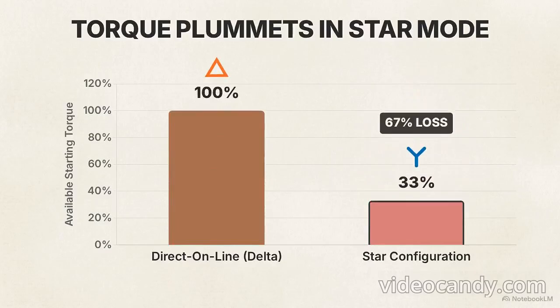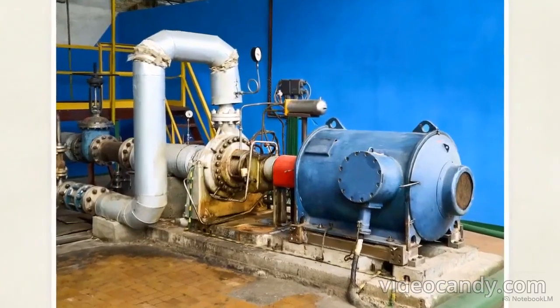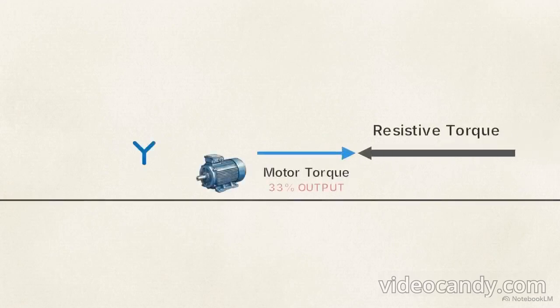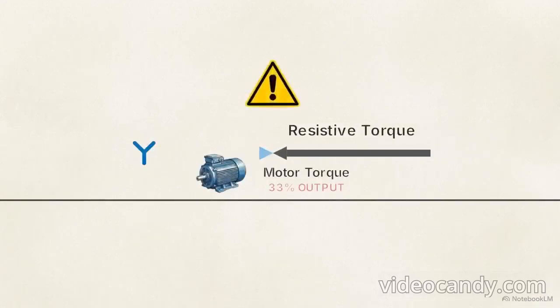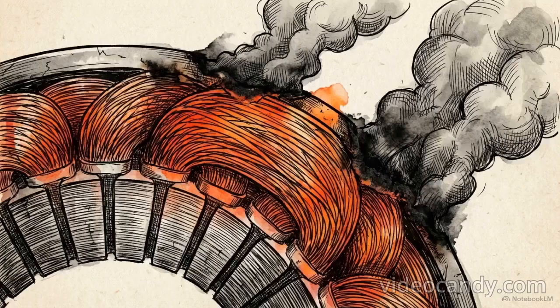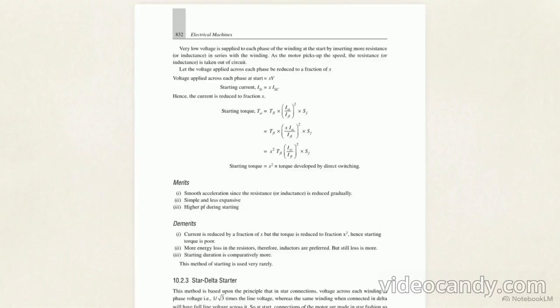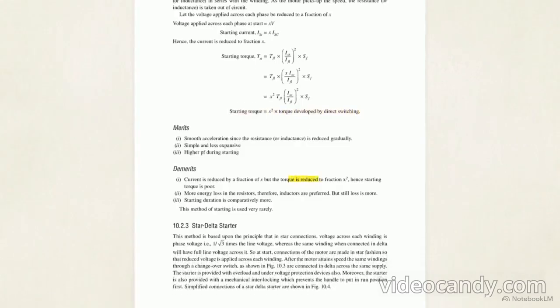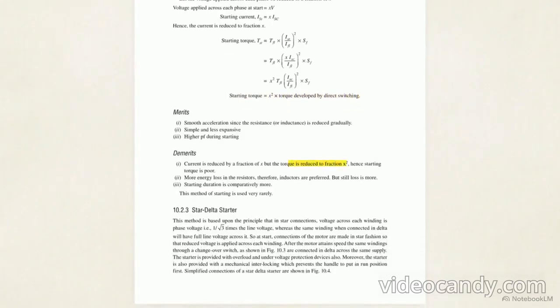The system has a severe engineering trade-off. While the starting current is safely slashed to 33%, the available physical torque is penalized just as heavily, dropping to roughly 25 to 33% of its initial direct online value. This creates a mechanical risk. Every load has a resistive torque. If the resistive torque of the machinery pushing back exceeds the motor's weakened torque in the star configuration, the rotor will stall, the current will spike, and the windings will burn out.